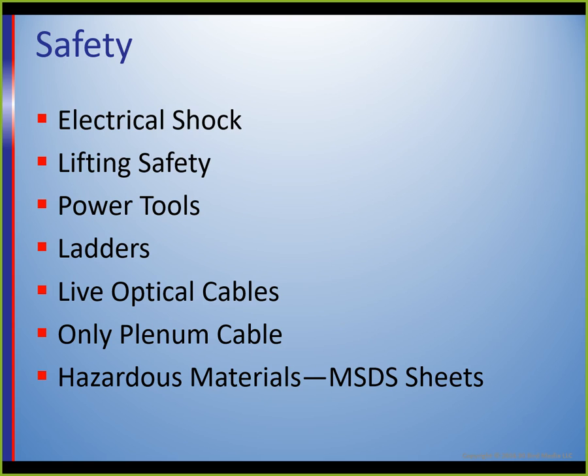Safety, electrical shock, always going to be an issue. When I was in the A school, when we worked on electrical equipment, we had to take off all of the metal rings, watch, anything like that, and work with one hand. The reason you want to work with one hand is the path for one hand is down the arm, down the body, through the leg, out the sole of the shoes. If you go with two hands, it goes across the chest, through the heart, and can cause some issues.